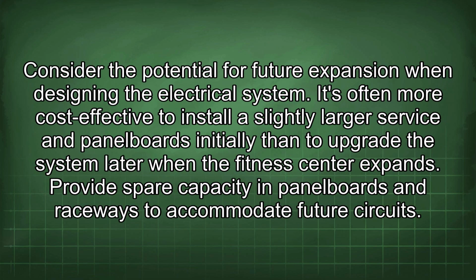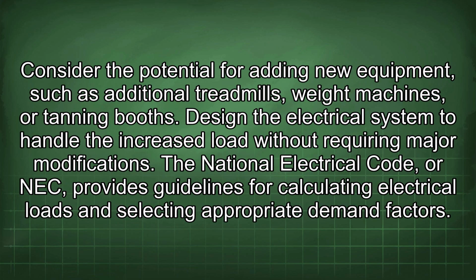Consider the potential for future expansion when designing the electrical system. It's often more cost-effective to install a slightly larger service and panel boards initially than to upgrade the system later when the fitness center expands. Provide spare capacity in panel boards and raceways to accommodate future circuits. Consider the potential for adding new equipment, such as additional treadmills, weight machines, or tanning booths. Design the electrical system to handle the increased load without requiring major modifications.